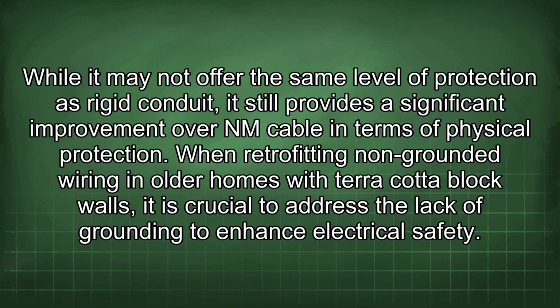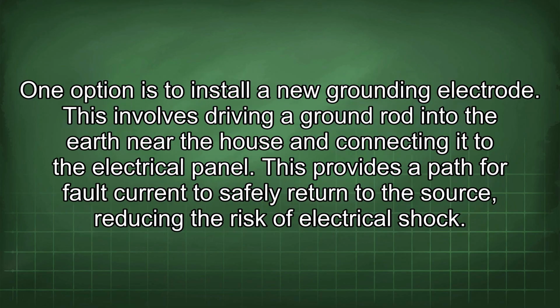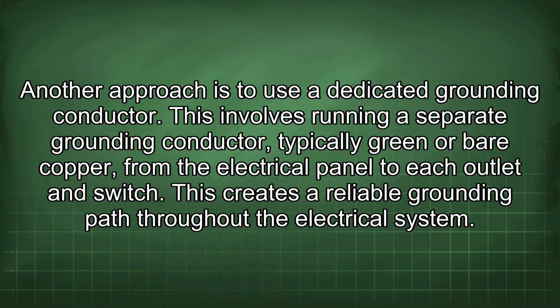When retrofitting ungrounded wiring in older homes with terracotta block walls, it is crucial to address the lack of grounding to enhance electrical safety. One option is to install a new grounding electrode. This involves driving a ground rod into the earth near the house and connecting it to the electrical panel. This provides a path for fault current to safely return to the source, reducing the risk of electrical shock. Another approach is to use a dedicated grounding conductor. This involves running a separate grounding conductor, typically green or bare copper, from the electrical panel to each outlet and switch. This creates a reliable grounding path throughout the electrical system.